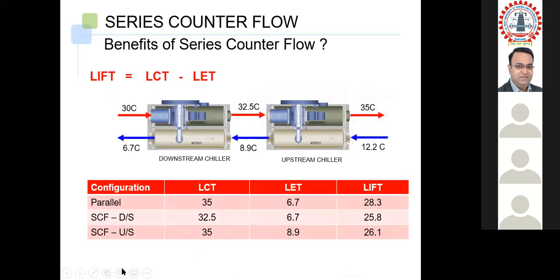So the ultimate benefit is what we have compared here with the parallel configuration. LCT stands for leaving condenser water temperature and LET stands for leaving evaporator temperature. The delta T between the two we call lift in general terminology. So you see here the lift in a parallel chiller configuration is 28.3.